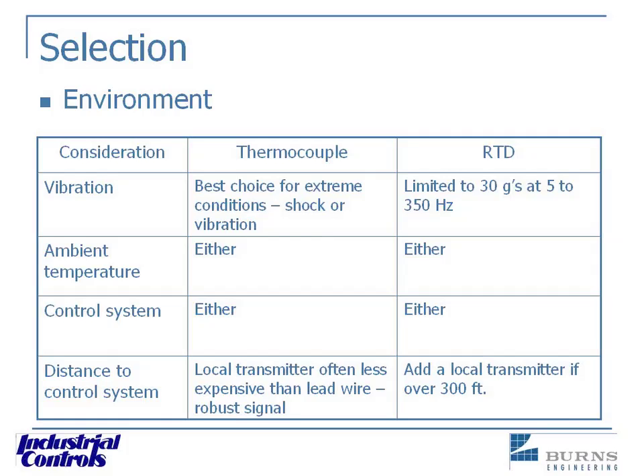The RTD, on the other hand, is just a standard 3-conductor copper wire, and there's less trouble, fewer problems with having that located a long distance from your control system. In either case, though, if you're running over, say, 250, maybe 300 feet between the temperature sensor and your control system, you may want to consider adding a transmitter locally right at the temperature measurement point. That way you get a much more robust signal going back to your control system. We see transmitters being placed on thermocouples and RTDs a lot.